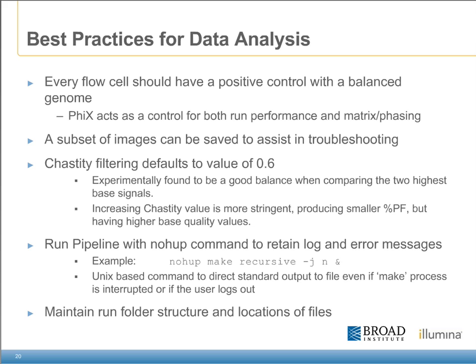The first of these is the use of a positive control with each flow cell. Illumina recommends the use of a Phi-X control lane to ensure run performance, as well as the correct calculations of both matrix and phasing. As our software has continued to improve, the saving of images is no longer necessary. However, a subset of images can be saved to assist in troubleshooting should anything go wrong chemically or with the instrumentation. It's also important to maintain a chastity value of 0.6, which has been experimentally found to have a good balance when comparing the two highest base signals. Although increasing the chastity value is more stringent, it could produce a smaller pass filter number with higher base quality values.